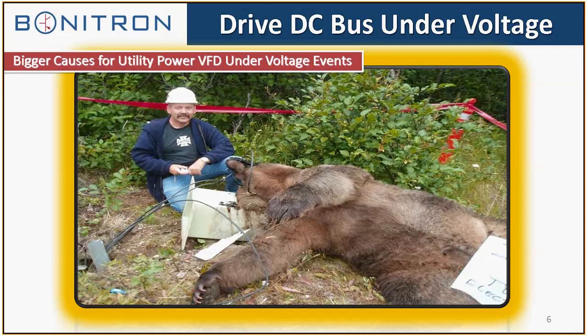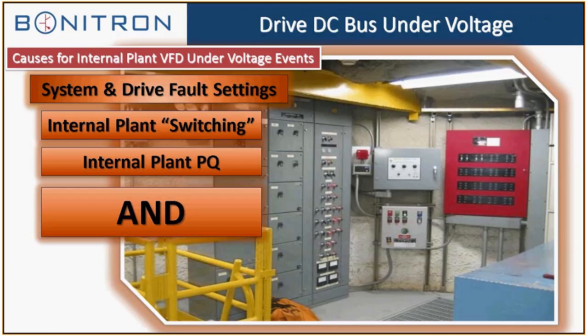This is another utility power event, and you have a variety of them, from cars hitting telephone poles to transformers blowing up to Smokey the Bear here. And that's what we're dealing with. We're dealing with the time it takes from the utility power event to the time that the utility company gets it back up and running. And that's usually where your specification comes from. It can be anywhere from utility power off up to gen set up. We'll talk a little bit about redundancy as we go along. Depending on the nature of the application, some applications require several levels of redundancy.